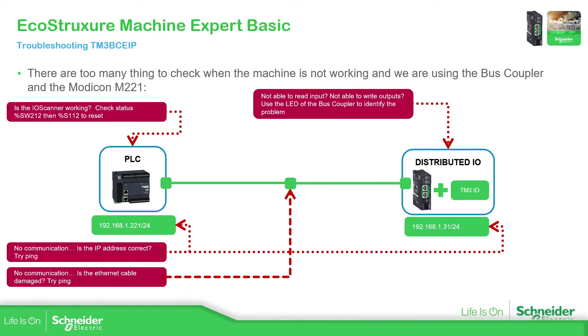The first thing that we need to check: if you're using Modbus TCP, we need to check if the bus coupler is configured as Modbus TCP or EtherNet/IP. That's something that we need to check on the PLC side.